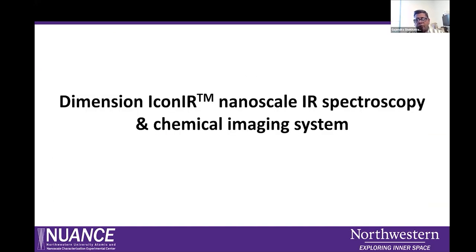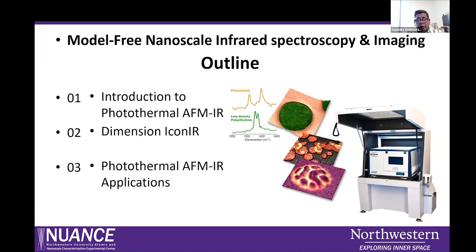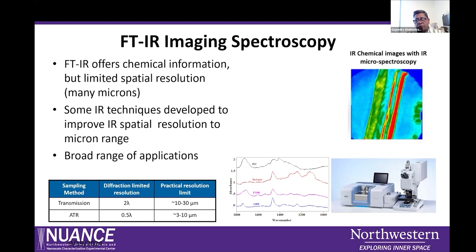Now the system we have is the Dimension IconIR system. I will give a little introduction about that. Then I will discuss what types of systems we have and what different modes and options we have on the system. This technique is also called photothermal AFM-IR because you are using those pulses to thermally expand the material, so it is also a photothermal AFM. In conventional FTIR spectroscopy, you can see here, they provide the chemical resolution. We have that system in the CAC2 facility, but it has limited spatial resolution, many microns. There has been a little improvement over that technique in the last couple of decades, but with the integration of this IR system with the AFM, the resolution is really pushed down to a few nanometers.